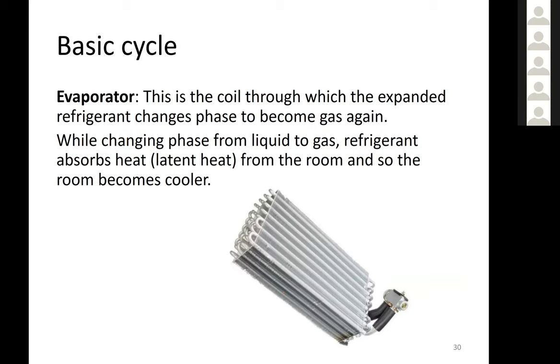In the evaporator side, of course, we have the inlet that comes from the expansion valve and goes through the coil. Inside these coils, I have the phase change that goes from a liquid-vapor mixture into almost all vapor, by the transfer of heat from the inside of the room to the evaporator. What do I need to do? This is just to have a fan. Why? Because I have the refrigerant already at a temperature that's low enough, lower than the room temperature. It could be, for instance, 10 degrees C. I can select the boiling point at this pressure to be 10 degrees C. Then, of course, the heat is going to transfer from the inside of the room to the evaporator. Now, with this understanding, that will help me select the right refrigerant. I need to check the boiling point of the refrigerant again at the evaporator side.